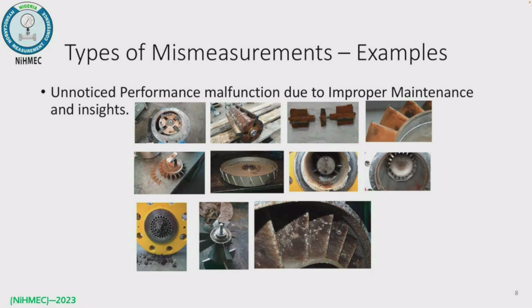Other common examples that we see are faulty settings, for example, bar A instead of bar G. Different ranges for transmitters. For example, a transmitter is set in the field with a range of 4 to 20 milliamps to be, for a pressure transmitter, 30 to 80 bar. But then in the flow computer itself, someone didn't put the setting right, and it is a completely different range. So it is receiving the right signal, but it's translating it to a completely different value. Incorrect K-factor adjustments is also something that we see going wrong many times. So calibrations that are not executed correctly, or the data not being entered correctly, and of course that has a major impact on the overall measurement uncertainty.